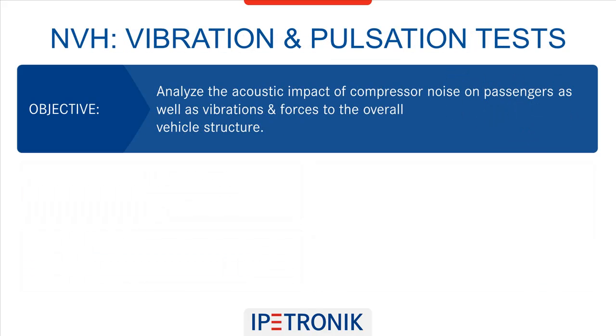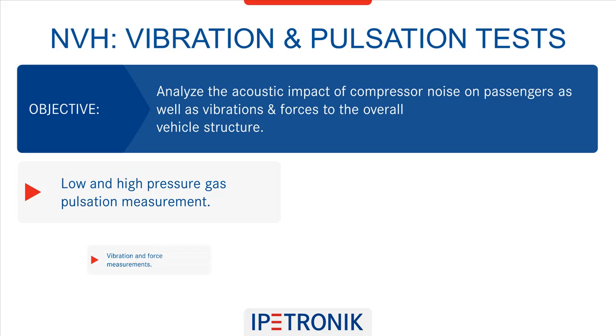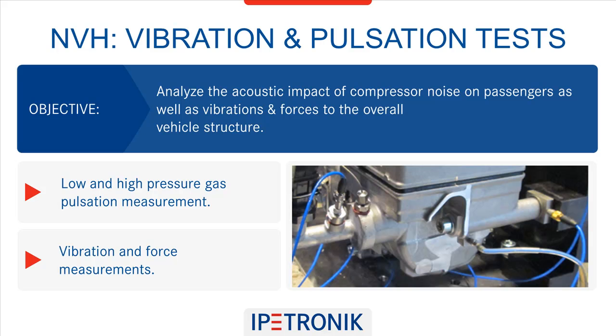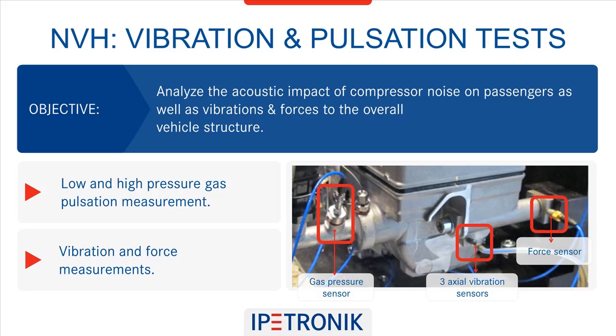During the NVH test, the noise and vibration impacts of the compressor are analyzed. One part of this test measures gas pressure and gas pulsation at the low-pressure intake and high-pressure outlet sections. It also looks at gas pulsation-caused negative impacts on the compressor and the HVAC circuit. In the image on the screen, you can see the application of a gas pulsation pressure transmitter. Other important analysis components include compressor vibrations, taken from 3 axial accelerometers, and their frequency and amplitude of forces impacting the mounting. Together, these forces can have a significant negative impact on the HVAC pipeworks and the vehicle structure.